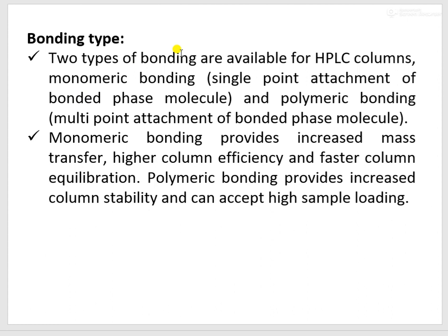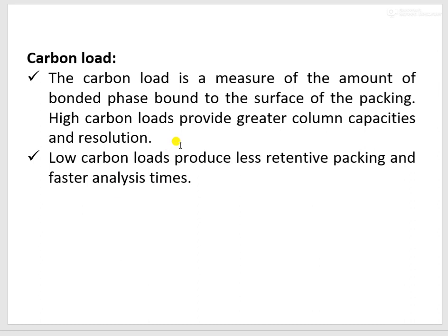Coming to bonding type — two types of bonding are available for HPLC columns. One is monomeric, which is single-point attachment of the bonded phase molecule, and the other is polymeric bonding, which is multipoint attachment of the bonded phase molecule. Monomeric bonding provides increased mass transfer, high column efficiency, and faster column equilibrium. Polymeric bonding provides increased column stability and can accept high sample loading. Next is carbon load — the carbon load is a measure of the amount of bonded phase bound to the surface of the packing.